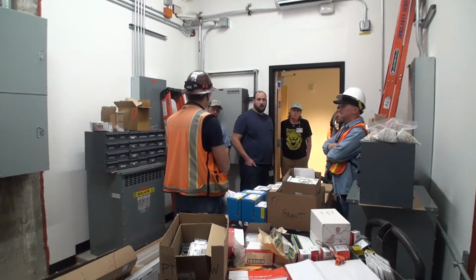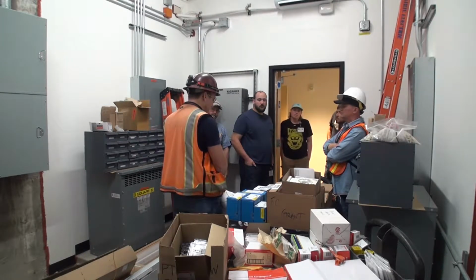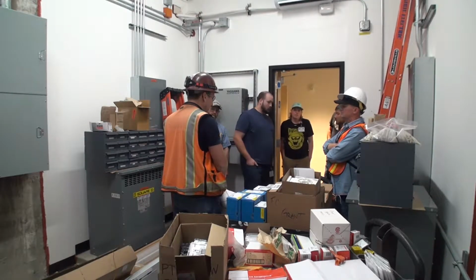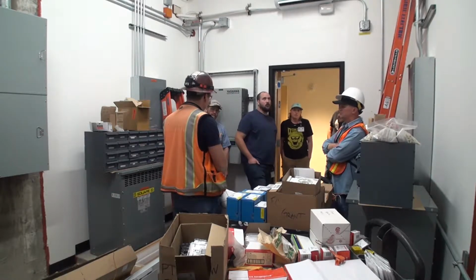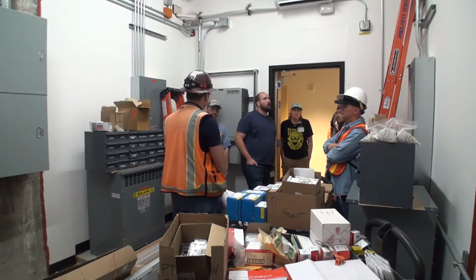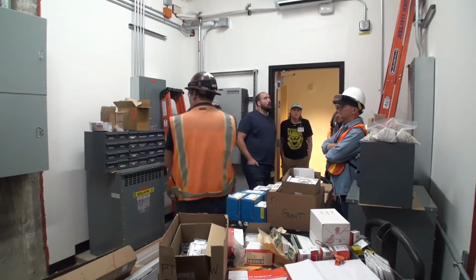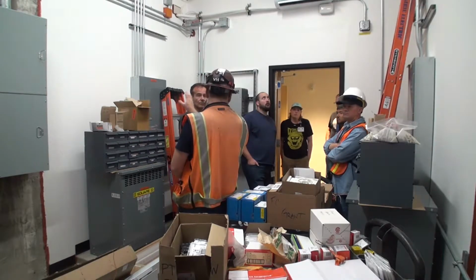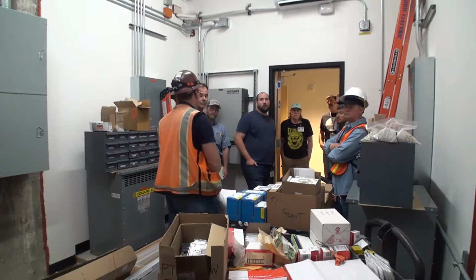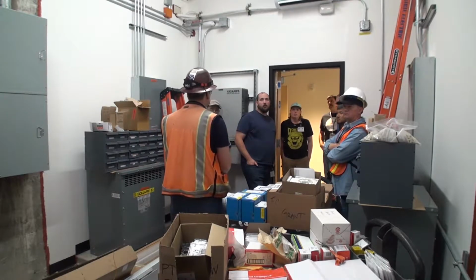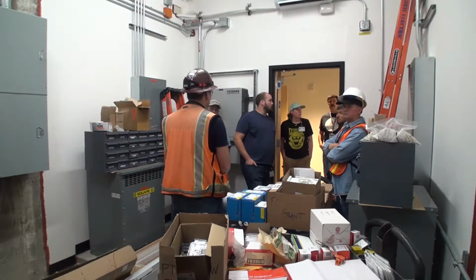The system is fully rated. It was a 600 amp feed. It can handle both, but as the code is written, once we get through the transfer switch and down the line, you cannot feed any non-emergency systems with it.